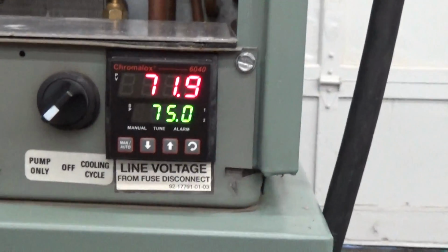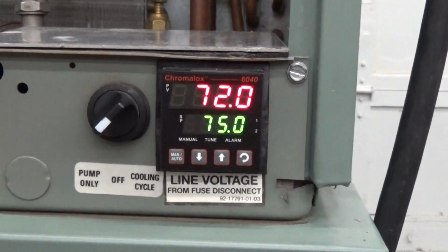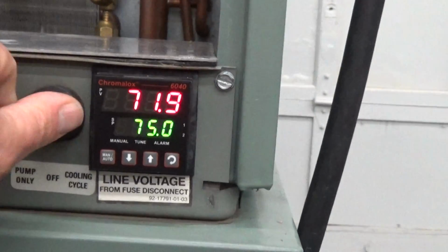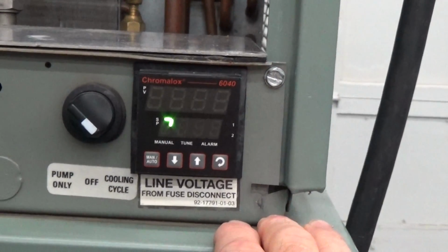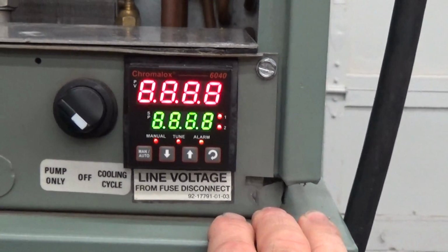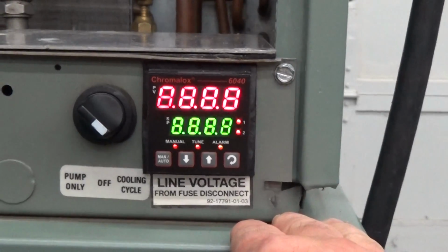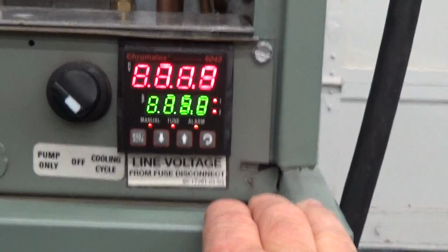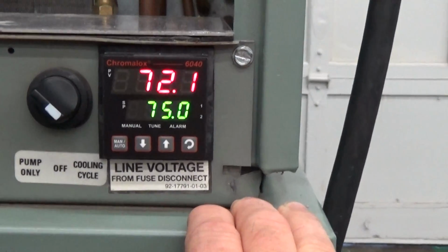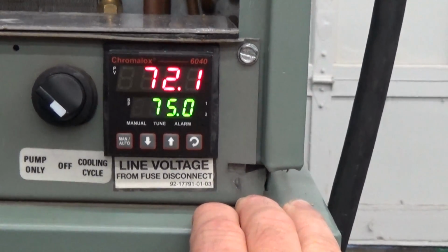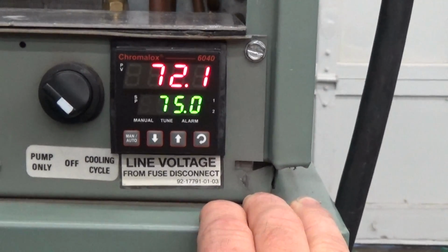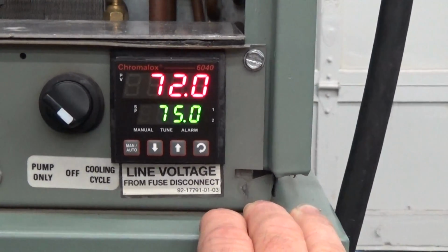This is a brand new controller we just installed. So I'm going to turn it into the cooling cycle right now. And when you get that little surge in power, it takes a couple seconds for the controller to reboot and do a little bit of a self-test. We've already set all the relevant settings inside the controller here. Right now we only have the tank about half full of 50% glycol, so we can chill down to about 30 degrees.